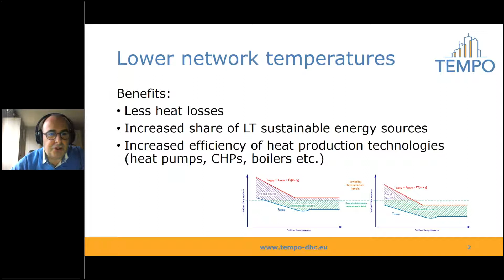How can we lower the network temperatures? If we do, the benefits are less heat losses in the district heating networks, an increased share of low temperature sustainable energy sources, and increased efficiency of the heat production technology. For instance, if you have a heat pump system connected to a district heating system, this will give you higher efficiency with lower network temperatures.